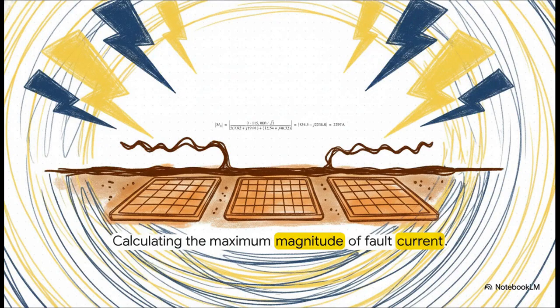Take a look at this IEEE formula. This is how we calculate the maximum magnitude of a zero-sequence fault current. Don't worry, we aren't going to memorize the variables today. But the big takeaway here is what this math represents. It calculates the absolute ceiling, the maximum electrical current that will dump into the earth if the system fails. The result of this equation tells grid designers exactly how much copper and how many grounding mats they need to bury in the dirt to safely divide and dissipate that catastrophic energy before it melts equipment or hurts someone.